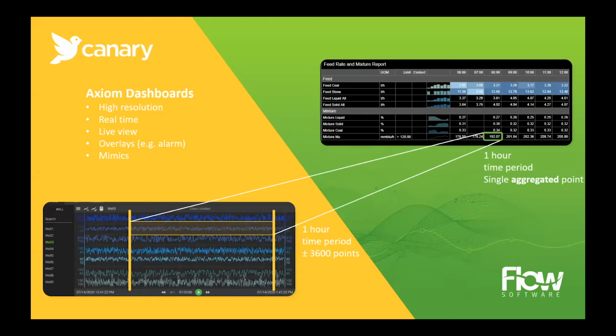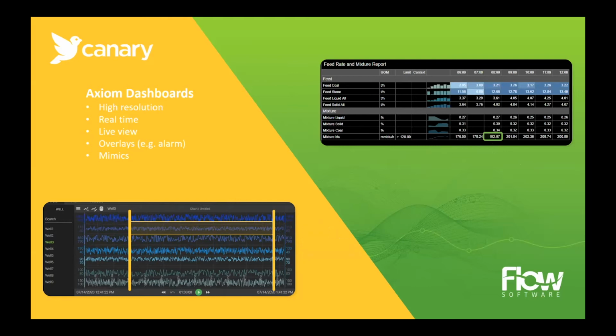Flow is going to take all of those data points, it's going to apply an aggregation method of your choice, and it's going to store a single value for that hour time period, a single aggregated value. And that is the value that gets stored and versioned in the Flow information platform. And that point for that hour becomes the single version of the truth.